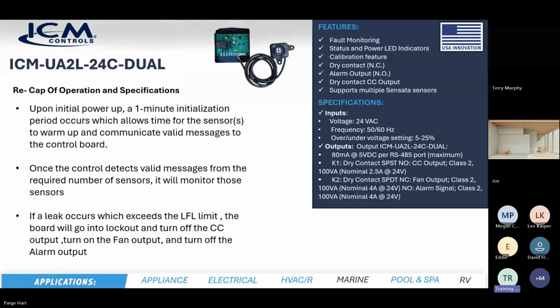So we have the first one from Bob Moore, and I think we answered the first part already. Can you use this in commercial applications? And the second part is how many CFM can the sensor handle? The second part, I do not know the answer to that. That's something that is very broad terminology used here, with the way that we have to set these things up. I don't know how many CFMs the sensor can handle, but it is designed to be used in the airstream. And remember, this is using the speed of sound. So it's not actually like concentrations. It's more or less how the concentration of refrigerant in the space affects the sound. Now, that being said, yes, it can be used in commercial applications.